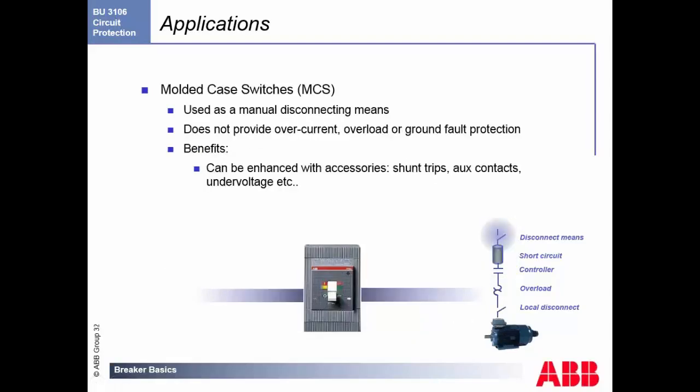Molded case switches (MCS), different than a breaker, because the switch is just going to open and close, is also required as a disconnect means above it. It does not provide overcurrent, overload, or ground fault, so you don't have the I protection that we talked about. You don't have the L protection that we're talking about. It can be enhanced with the shunt trips so that, again, you can see an overvoltage and pop this. But this is the guy that sits at the very beginning of the chain.